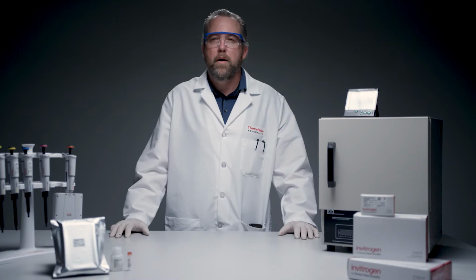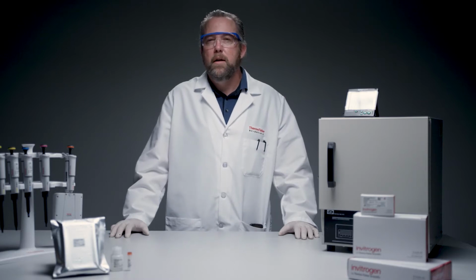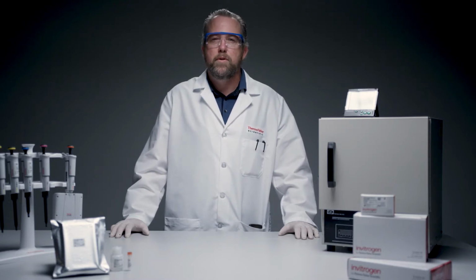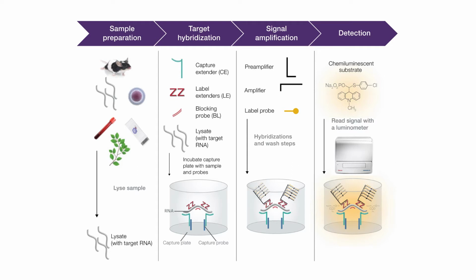Prior to setting up and running the QuantiGene Singleplex assay, calibrate the incubator or hybridization oven to both 55 and 50 degrees Celsius using our temperature validation kit. To properly set up the incubator, please refer to the how-to video or refer to the user's manual. Make sure that you have a microplate reader capable of luminescence top reading.